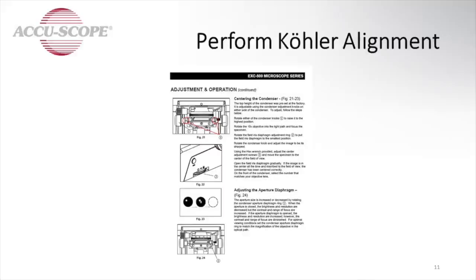The condenser aperture diaphragm should also be adjusted each time the objective is changed. You can find these steps in the EXC-500 manual and they only take seconds to perform.